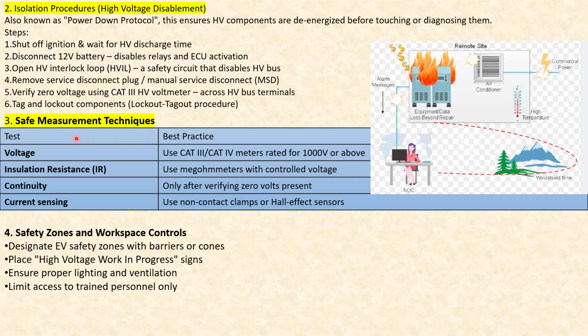Now, talking about safe measurement techniques. When it comes to voltage, use CAT 3 or CAT 4 meters rated for 1000 volts or above. For insulation resistance, use megohmmeters with controlled voltage, and check continuity only after verifying 0 volts is present. Now, talking about current sensing, use non-contact clamps or Hall effect sensors.